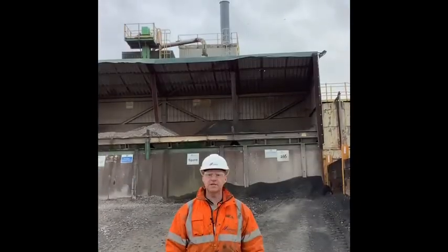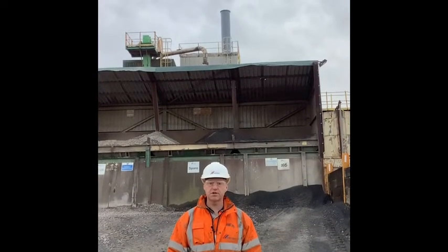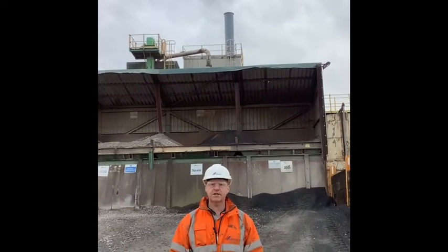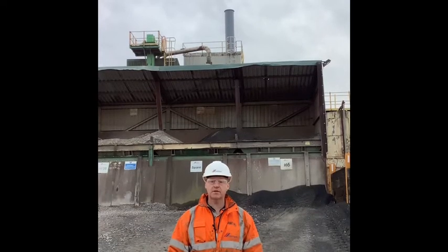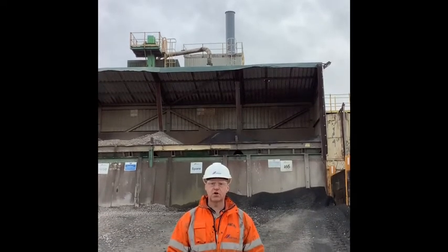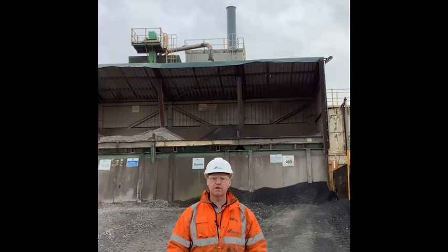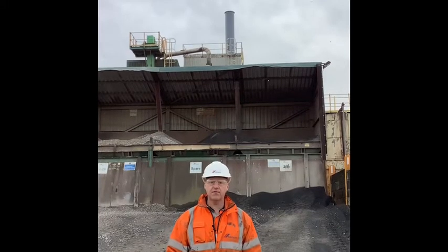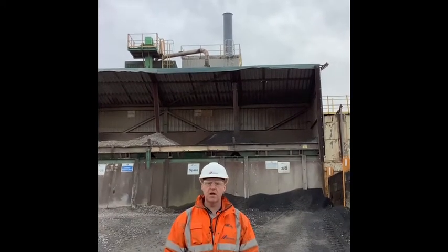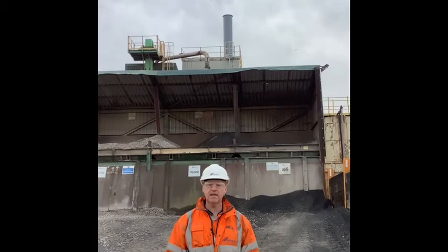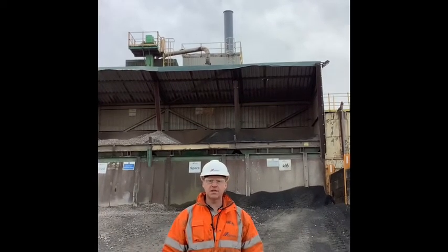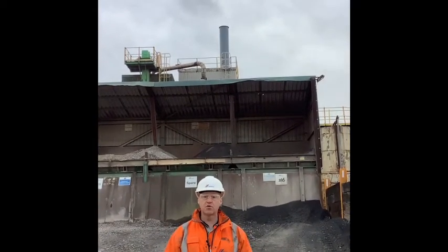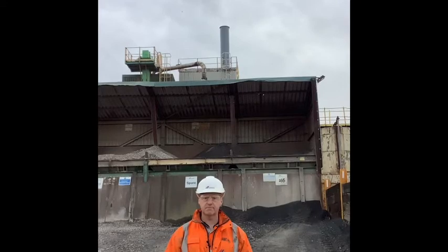One of the easiest daily checks to make sure that our stack is in good condition is to visually look at it. Coming up in a minute will be four shots of my stack taken about a minute apart. It's to try and show you the effect that the sun and different angles will make on the visual impression that your stack has. Have a look at them now and see if you notice any difference that the sun, the angle, the shadow makes. Do you think the stack looks clean? Is it billowy, silky steam emissions? Or does it look more sinister, such as filler or other particulates are involved in it?